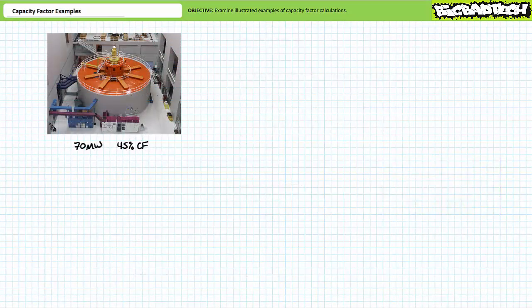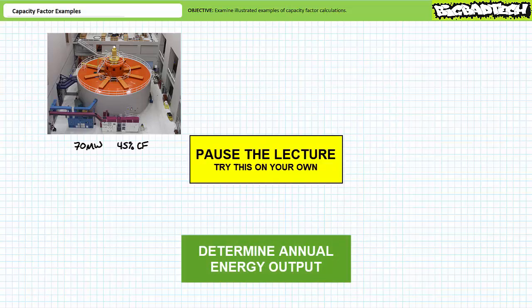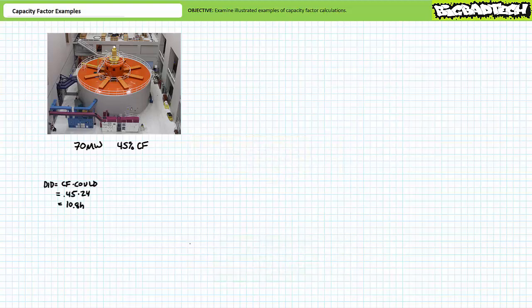Let's try some more practical examples of capacity factor. Consider a 70 megawatt turbine in a hydroelectric dam operating at a 45% capacity factor. See if you can determine how much energy this turbine would produce in one year — pause the lecture and try this on your own. If you're tracking, you should have obtained the following results. Capacity factor is a measure of how often the turbine runs at full capacity. A figure of 45% means the turbine runs at full capacity for 45% of each 24-hour day, or roughly 10.8 hours.